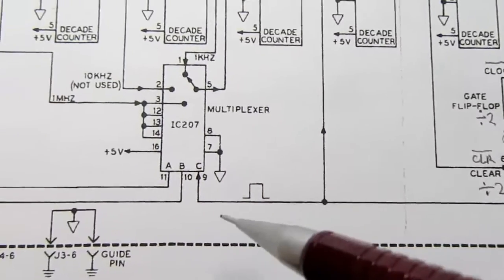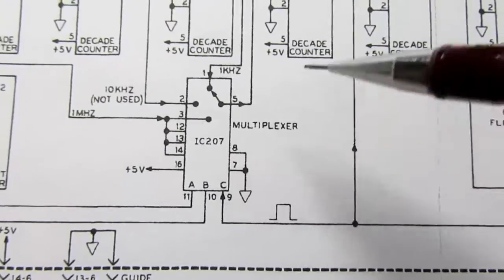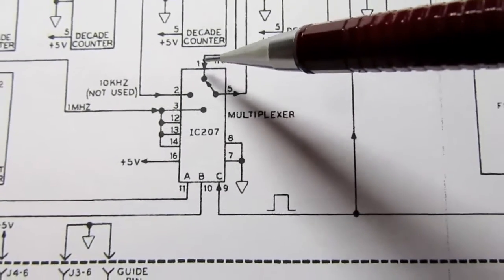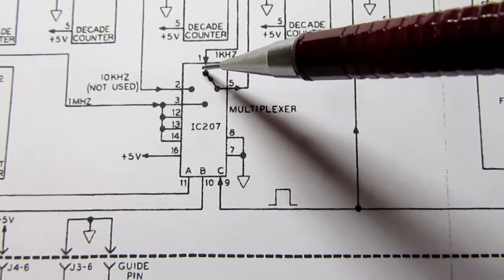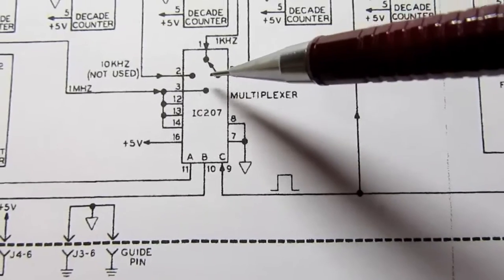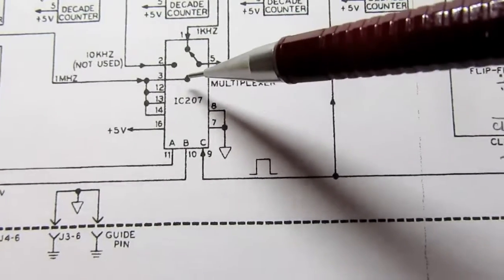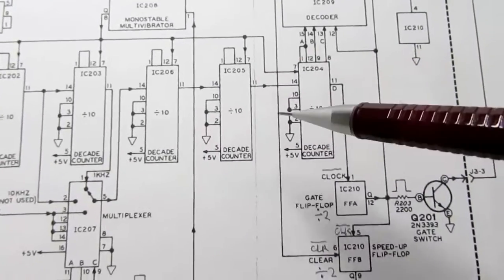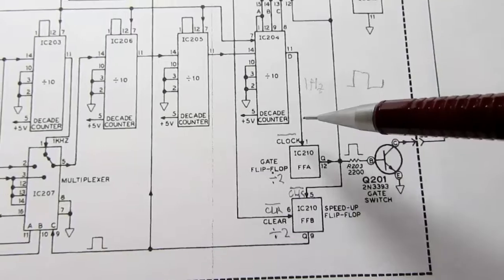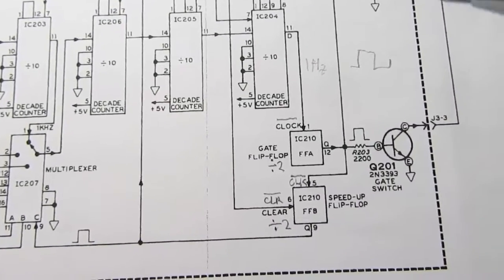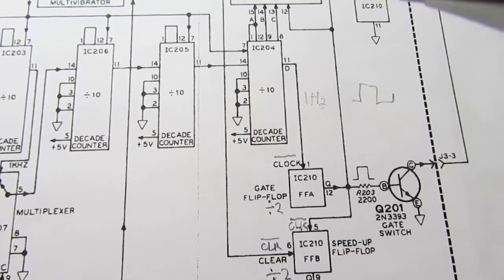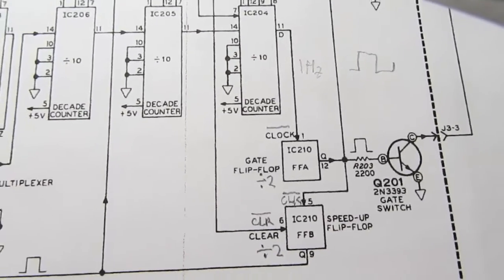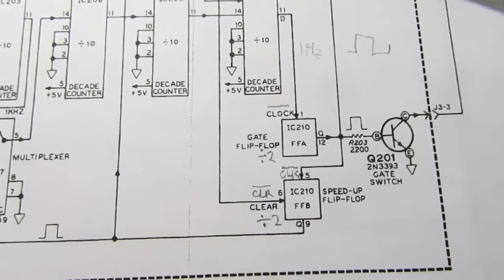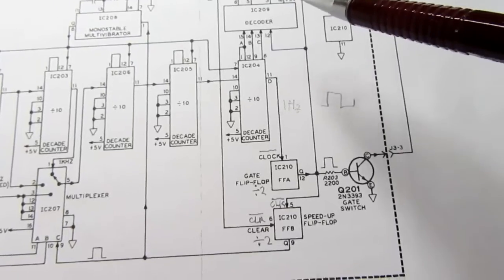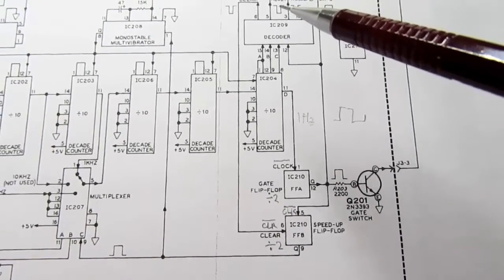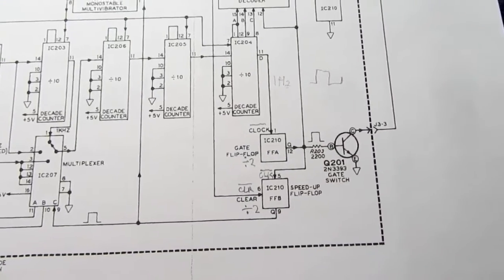So it reaches over here, and it goes into this multiplexer again. And what it essentially does is, even if we were in the 1 kilohertz position, it temporarily kicks it over to the faster position so that the final stages of processing after the count is done are sped up. Otherwise you'd have to sit there and look at the display for a longer time when you're in the 1 kilohertz mode and you have the 1 second gate signal. You'd be waiting additional time for the rest of this housekeeping to take place. But it doesn't need to be slow. The only thing that needs to be slow is the gate. After that, the rest of it can go a lot faster.